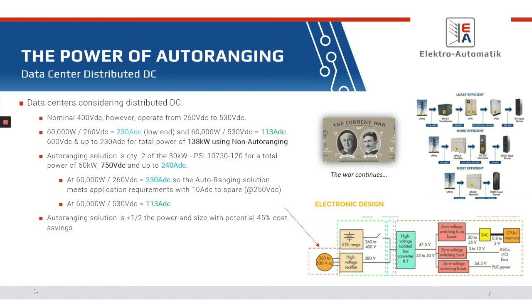And so, as a result, what they're looking at is providing DC voltage throughout server farms. The nominal voltage for this is right around 400 volts. However, they operate as low as 260 volts and up to 530 volts. So in this particular example, the server is still going to pull a full 60 kilowatts at that 260 volts DC. So you're looking at 230 amps, right? So that's the low end, the low voltage, high current condition. The other, likewise, is, hey, we need to go as high as 530 volts. Well, okay, your current's a lot less, but now you have to hit that 530 volts.